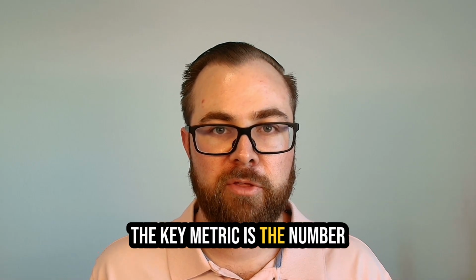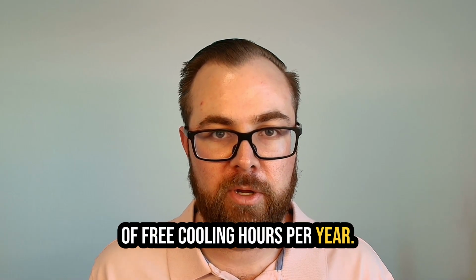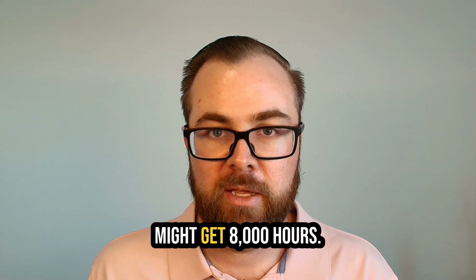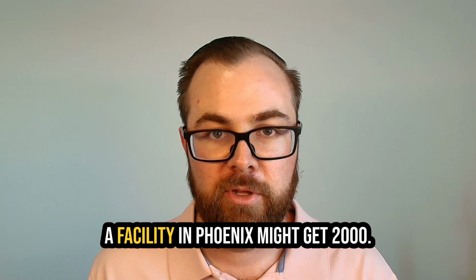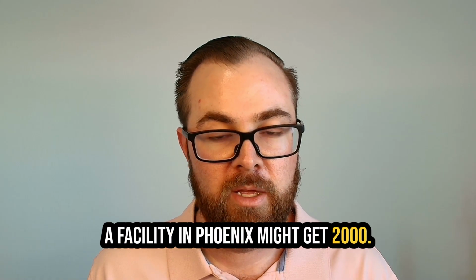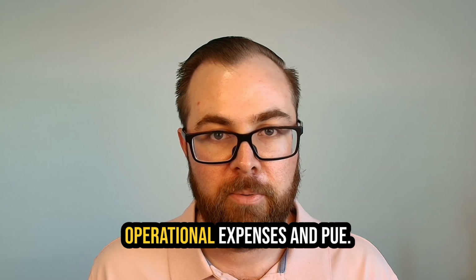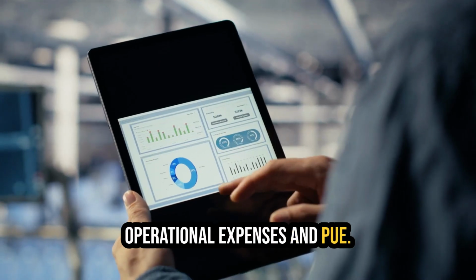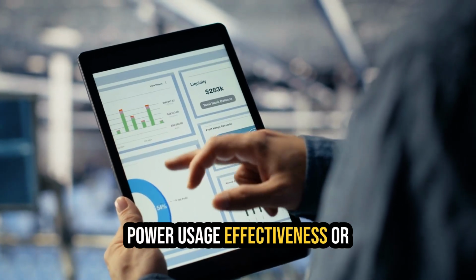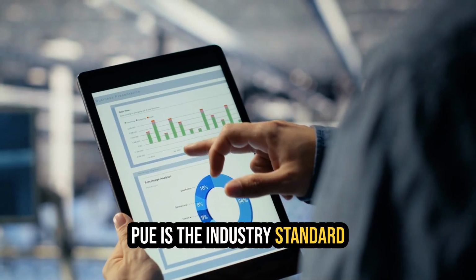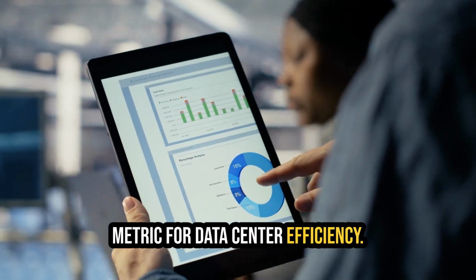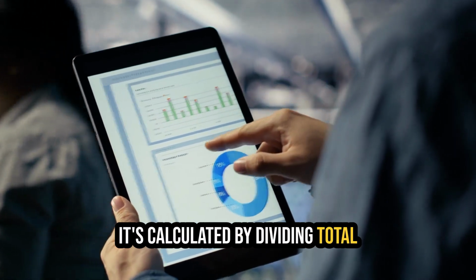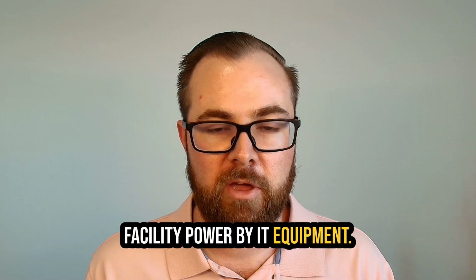The key metric is the number of free cooling hours per year. A facility in Iceland might get 8,000 hours, a facility in Phoenix might get 2,000. That difference directly impacts operational expenses and PUE. Power usage effectiveness, or PUE, is the industry standard metric for data center efficiency. It's calculated by dividing total facility power by IT equipment power.